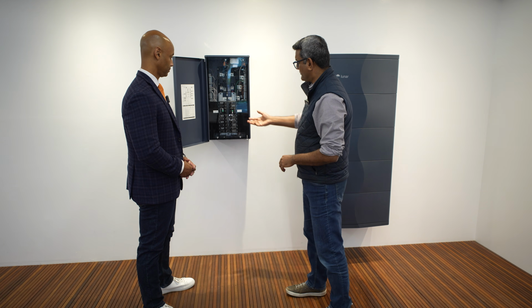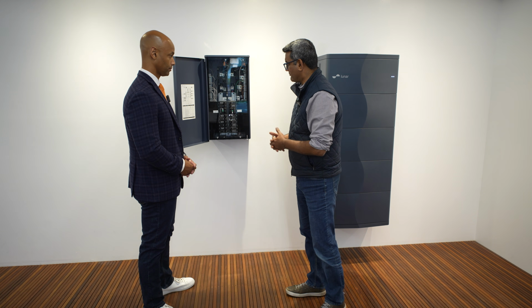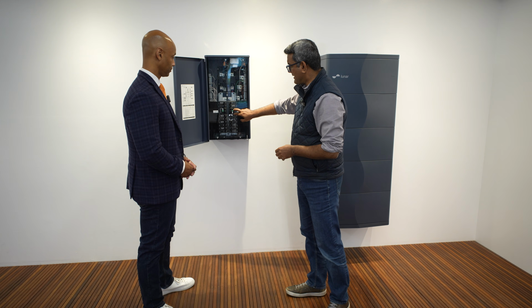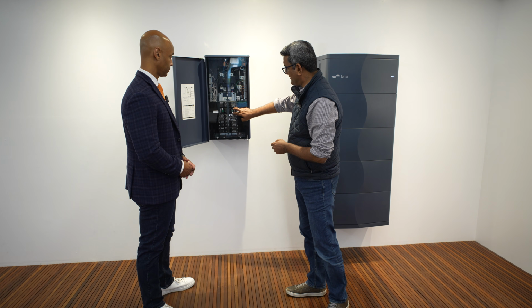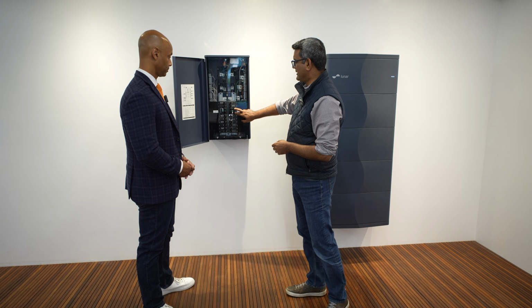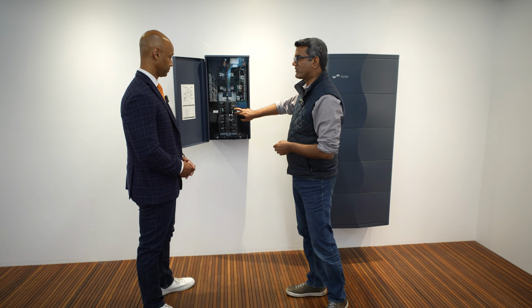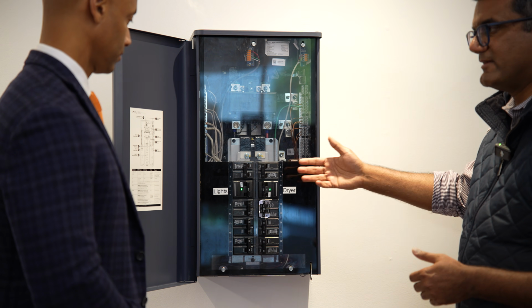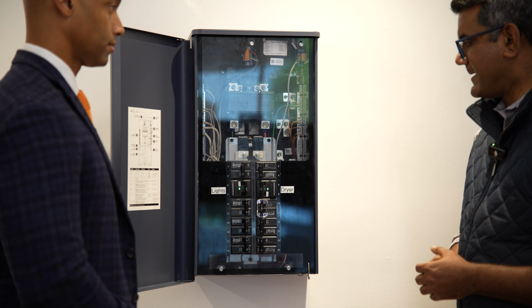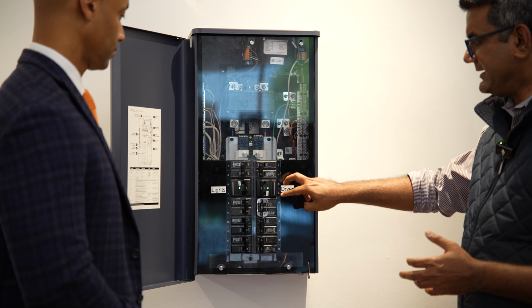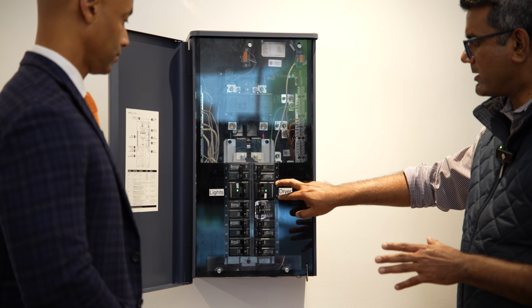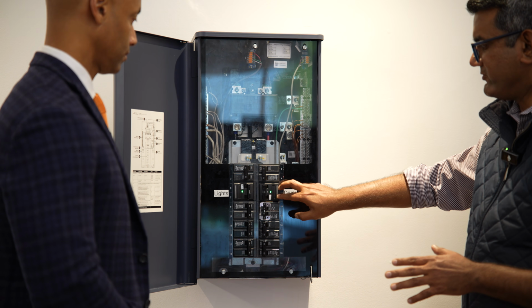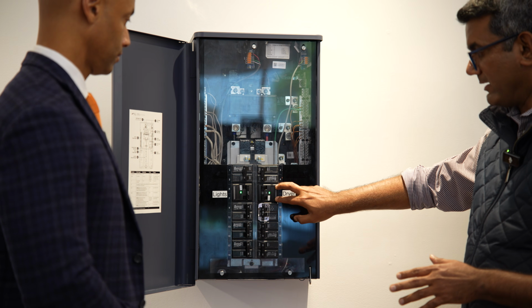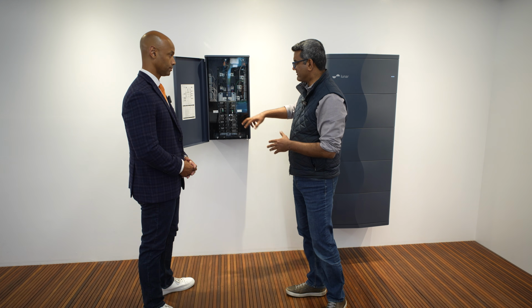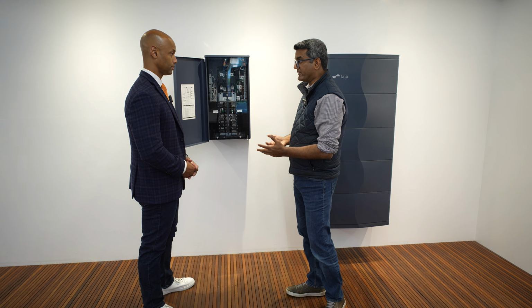We can go into the detail of load control at some point, but right now I can share that this is an Eaton smart breaker. It's a 2-pole 60 amp breaker, and they're coming up with 60, 50, 40 amp sizes. While we use an Eaton product, and they make a great smart breaker, this is also AFCI, GFCI capable, and it's fairly inexpensive compared to a full smart panel redo.